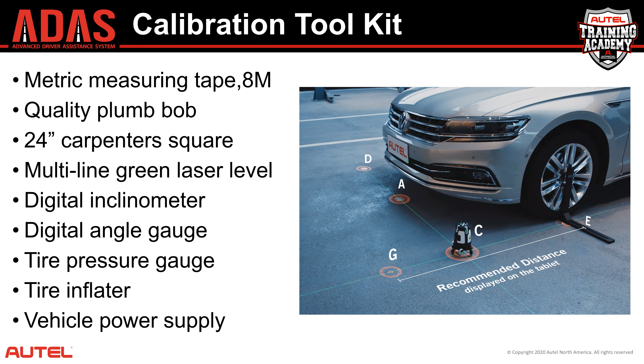Next is a digital inclinometer. This is a digital level, but it only measures level across 2 inches. Digital inclinometers are great for checking the plumb of a radar sensor. So here we're looking specifically at, is the face of the radar sensor exactly 90 degrees to the ground? You can see here there's a ratchet and a hex wrench attached to the adjustment screw, and you adjust it until it reads whatever value the OEM dictates.